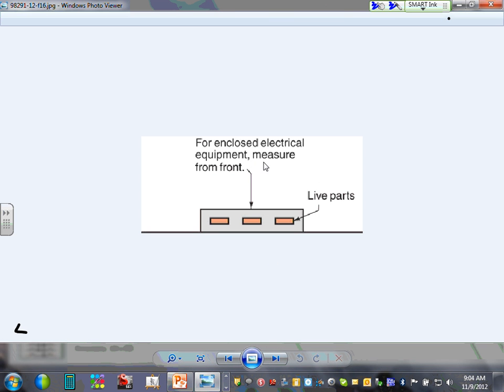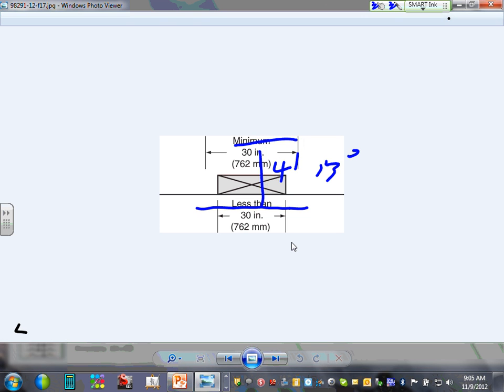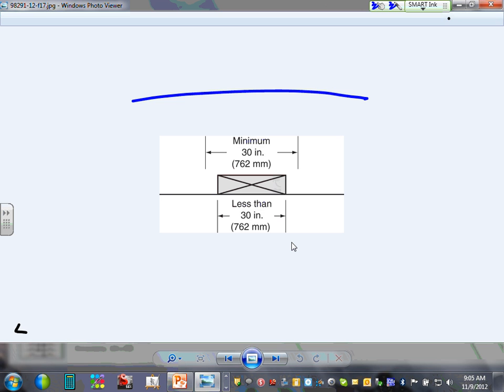Okay, for electrical equipment, the way they measure the feet, guys, they measure from the box right here. So here's where your 4 feet or 3 feet comes, or from the energized parts if it's open buses. We don't deal with open buses a lot. So from the outside of the enclosure. Now the second thing for the clearances is, here's my wall, and here's my clearance. And this is my 3.5 foot, because this is 480/277, right? From the code.